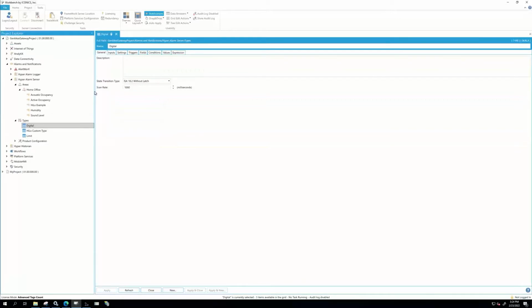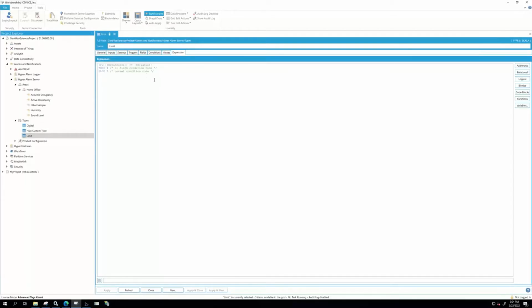The basic ones you get when you install it are a digital type and a limit type, instantiated whenever you create one here, but you can create many different types. If we look at a limit type, the expression is simply an if-then: if the data is higher than a certain value, then you've got an alarm. That was the case for sound level or humidity.